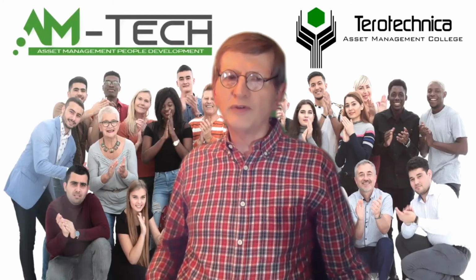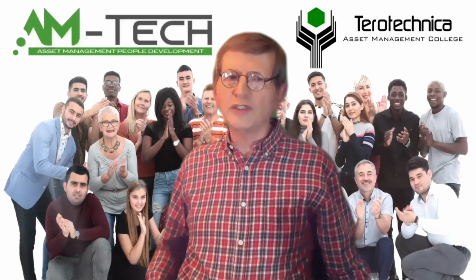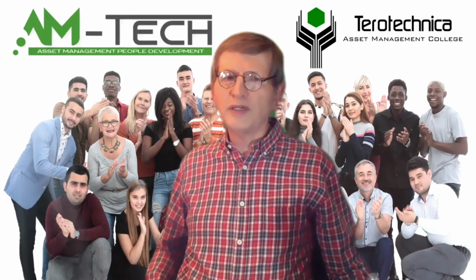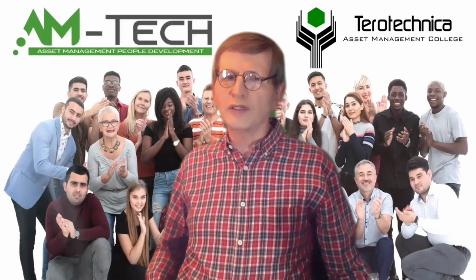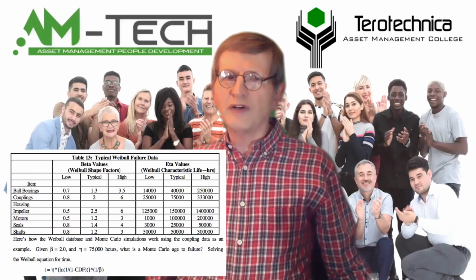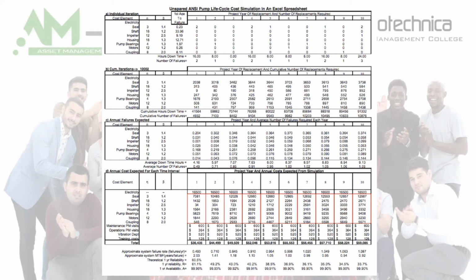Failure statistics can be improved considerably utilizing available Weibull distributions. These give better statistical representations for explaining the life and repair times for equipment. Weibull failure database information is available. That's Barringer 1996b, to supplement earlier mentioned failure data from Bloch and Geithner. A partial listing of the Weibull database is shown in Table 13. Recent papers describe how to put the Weibull database information to work. That's Weber in 1996. Table 14 shows how Monte Carlo simulation works for the unspared ANSI pump.